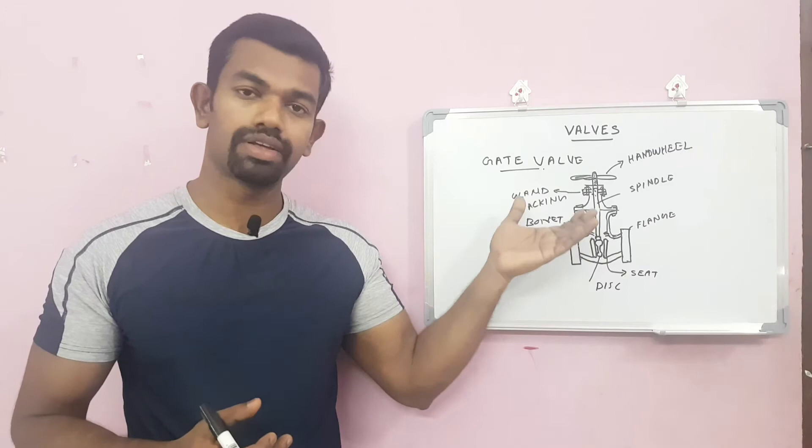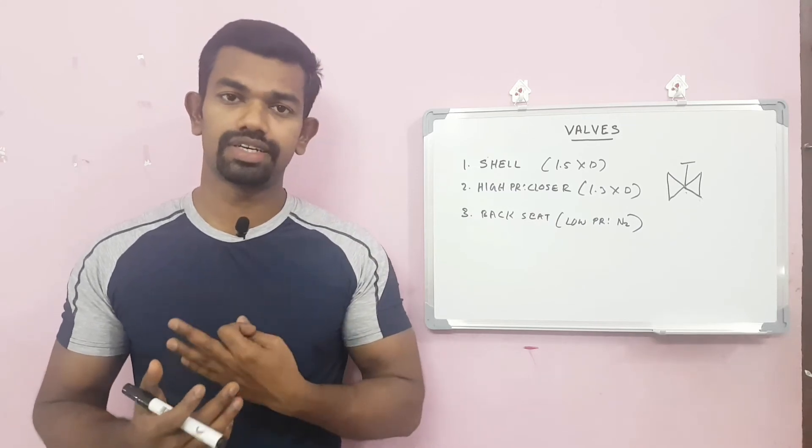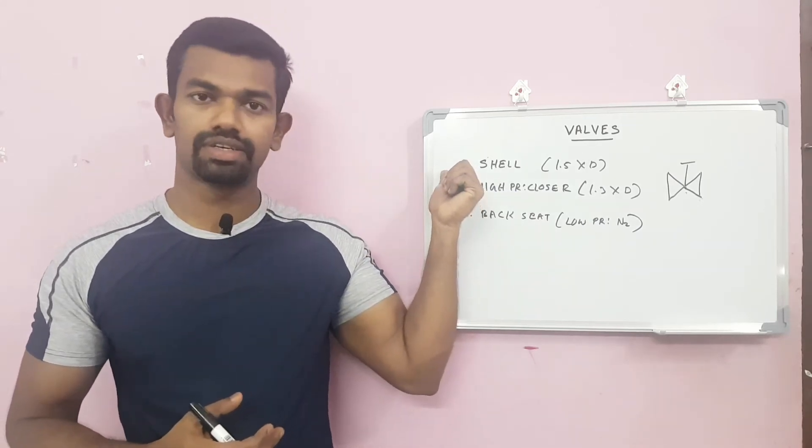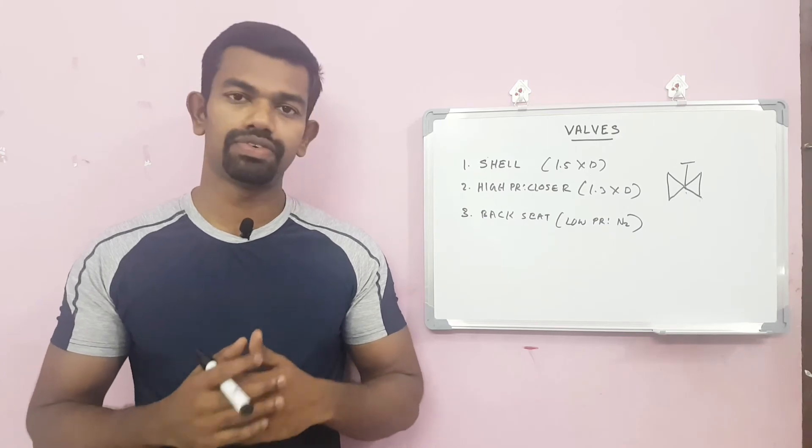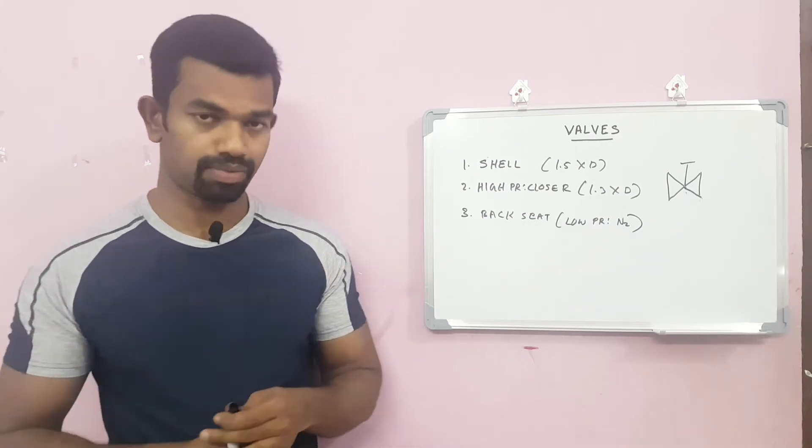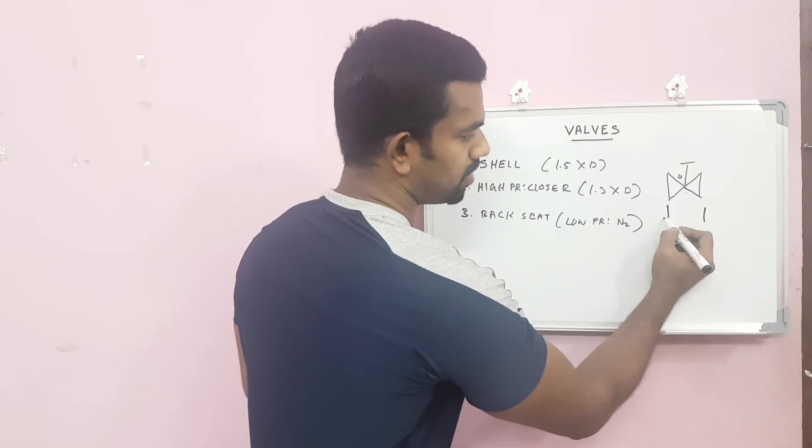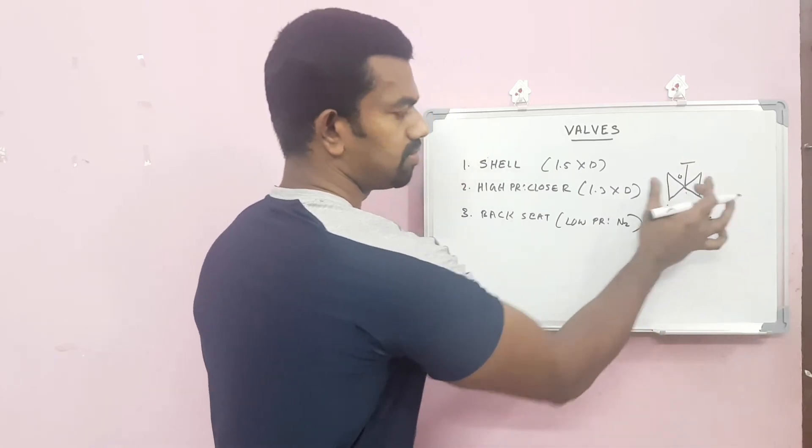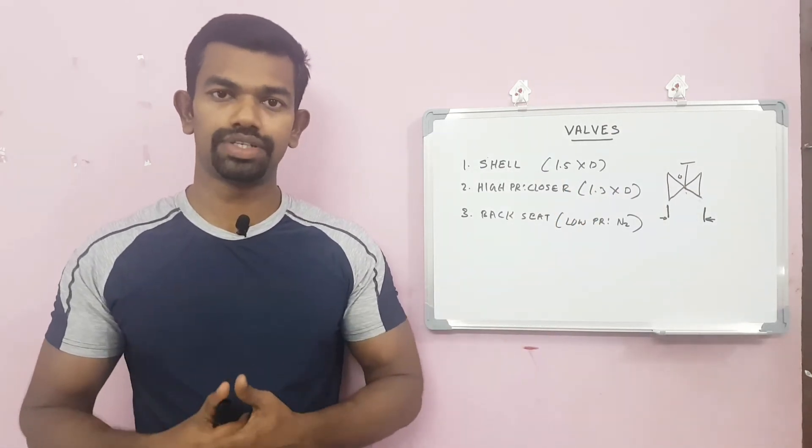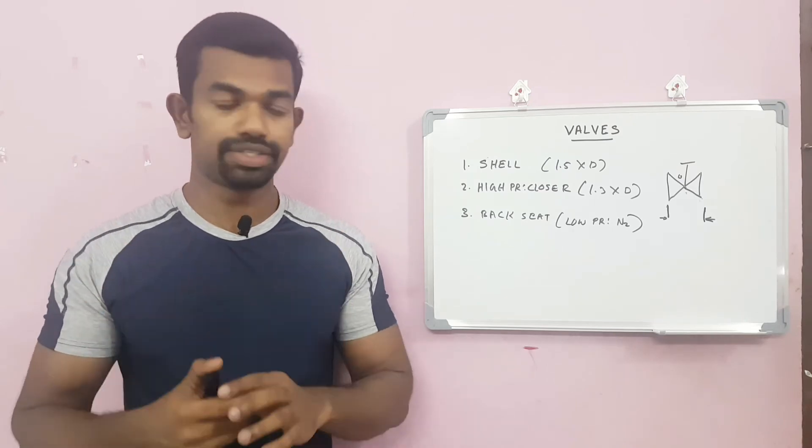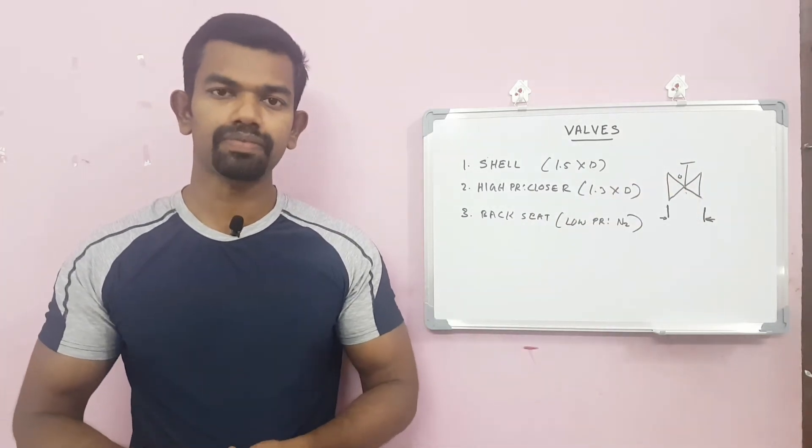Now we can take a look at the testing methods of a valve. There are three stages for testing the valve. First one is high pressure shell test. For the shell test, the valve will be in open condition and we will isolate both sides of the valve. The valve will be open and we will apply pressure on both sides with 1.5 times of design pressure. For example, if the design pressure is 20 bar, we will apply 30 bar pressure in this area. The valve will be in open condition. This is the shell test.